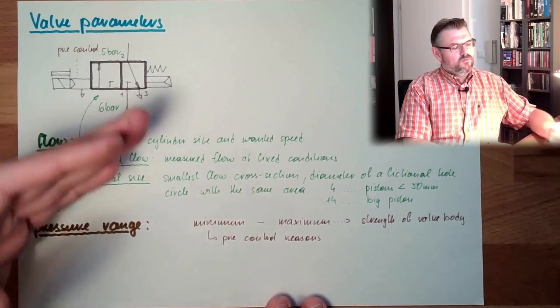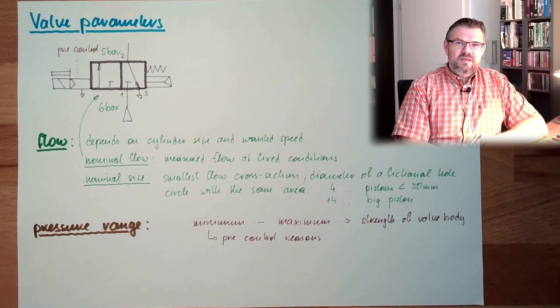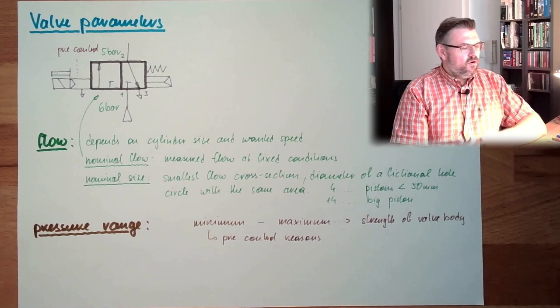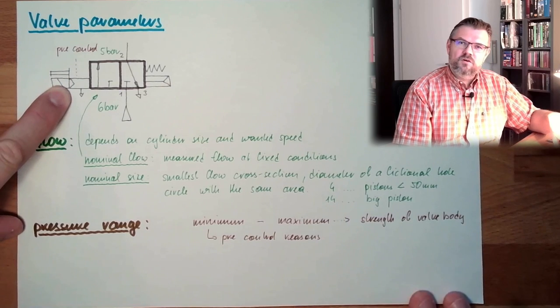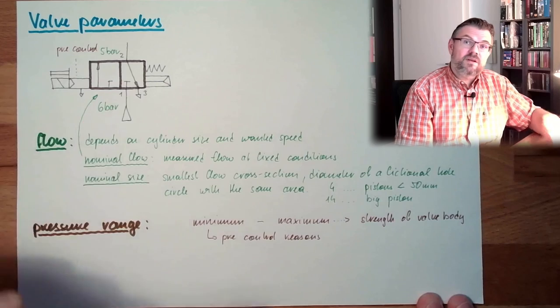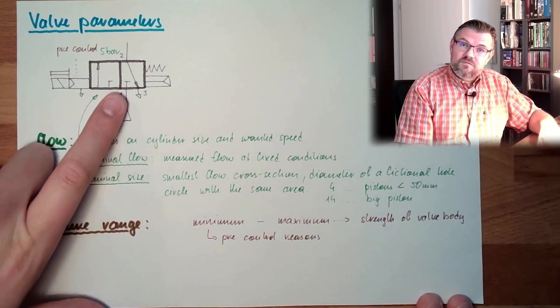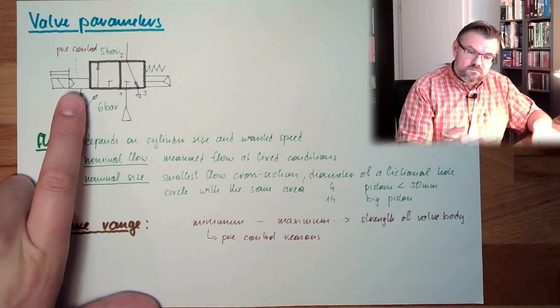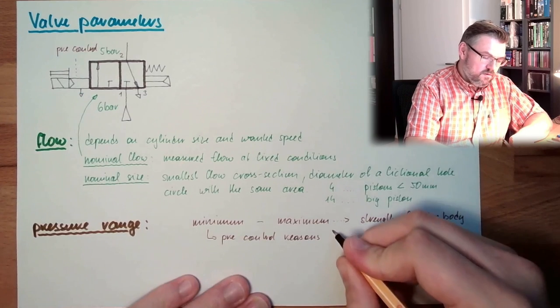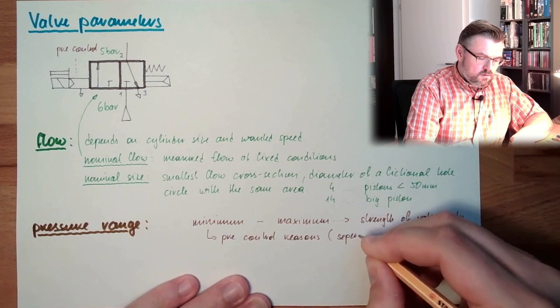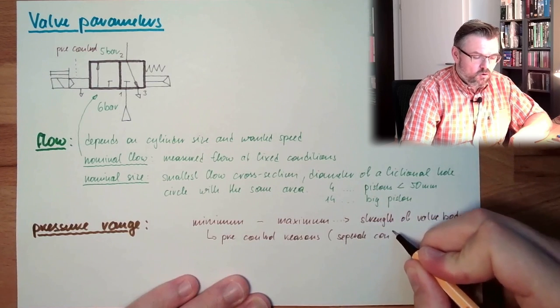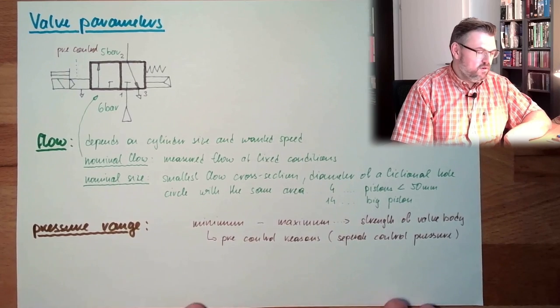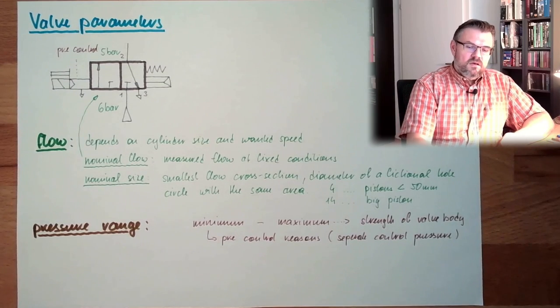But what if I want to control with a pre-control valve something which really does not need a lot of pressure, must not have a lot of pressure, what then? I'm at the end of the line, or what? No. There are also valves which do have a separate pre-control pressure connector. If the operating pressure, where the pre-control pressure is usually taken off, is not sufficient to meet your minimum pressure, then you need to select a valve with a separate pre-control pressure. So, separate pre-control pressure might be the solution, then, in your application.